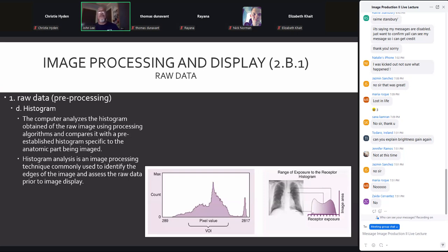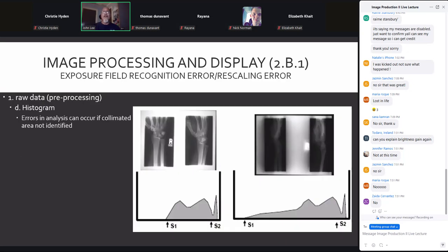So with our histogram, the computer is going to analyze the data. Once it's gone through the analog to digital converter, it's going to generate a graph, a pixel count, if you will, of different values. It's going to determine, based on the algorithms that are already inside the system, what parts are outside what we refer to as the values of interest. And the values of interest are those values from low to high, which should correspond to specific anatomy. Once it identifies the values of interest, it can make an adjustment based on the lookup table.